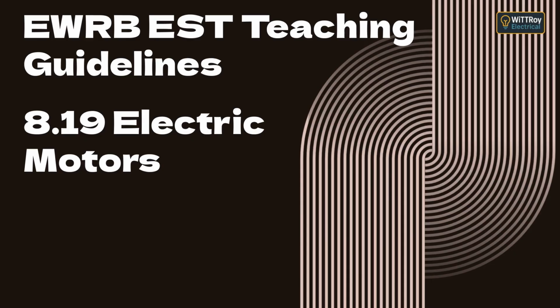2. Short circuit protection. This protects against high fault currents caused by insulation failure or wiring faults. Fuses or miniature circuit breakers, MCBs, are used for short circuit protection. They operate almost instantaneously to prevent cable and winding damage.